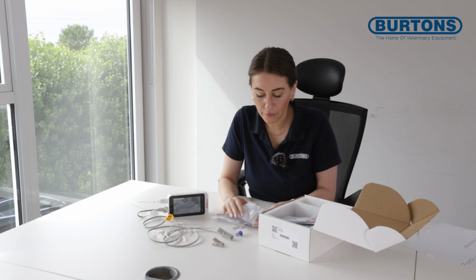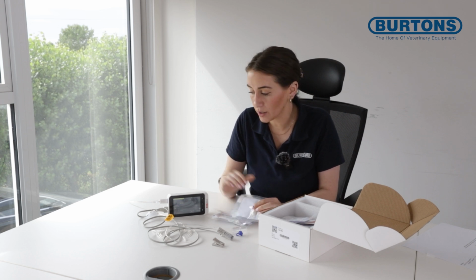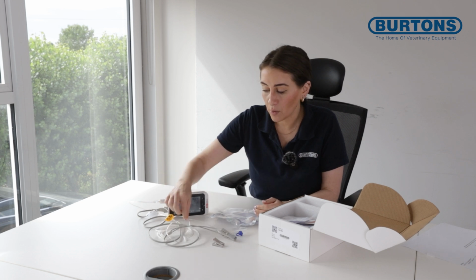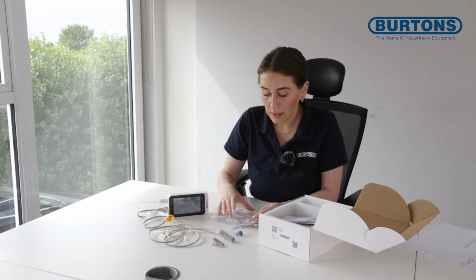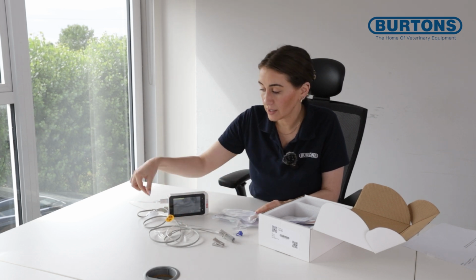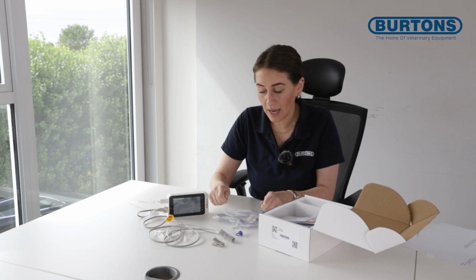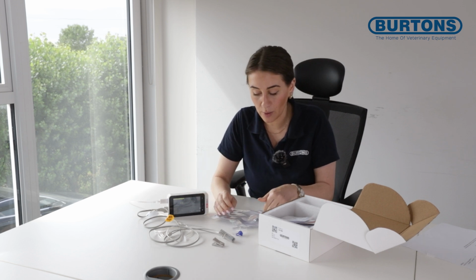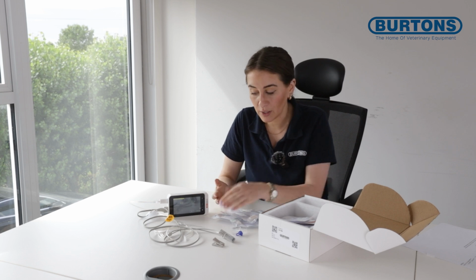To try and preserve the life of the filter, we'll always want to disconnect it, which will stop pulling air through it, and we always want to disconnect our sample tube as well. So to try and preserve this, we'll disconnect our sample tube and try and hang it down so that we get the water vapor to drip with gravity. Typically people will do that at the end of the day to try and preserve the life.